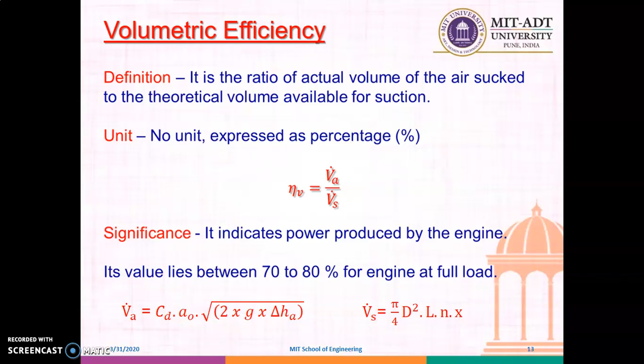Actual volume of air sucked is calculated by the formula Cd into area of the orifice A0 under root 2g, that is gravitational acceleration, into delta H, that is a pressure drop measured in terms of air column, delta Ha. And the stroke volume, that is the V dot S, is calculated by the formula pi by 4 d square into L into N into x. At this moment, you just remember these formulas.